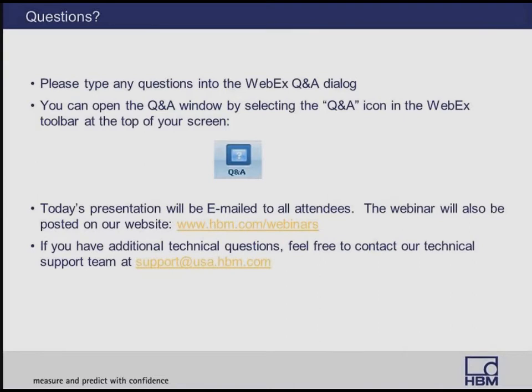An attendee has a quality assurance application where they want to measure the dimension and thickness of materials as well as tolerances. The sensors they're using are white light interferometers that give out a 0 to 10 volt signal. So he's wondering if PMX would be useful for this application. Yes, it would be. Basically they'd like to compare the data of a perfect QA specimen to the data collected on a newly manufactured unit. Yes, you can. PMX has a voltage and current input module, the 401. You would use that and feed in your output from the device, and you'd be able to measure it directly.